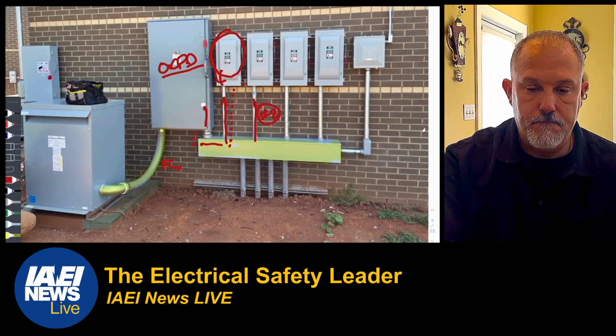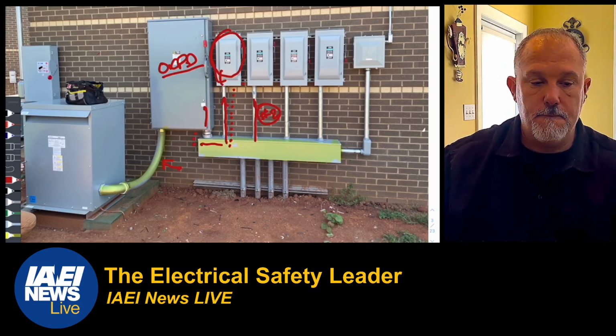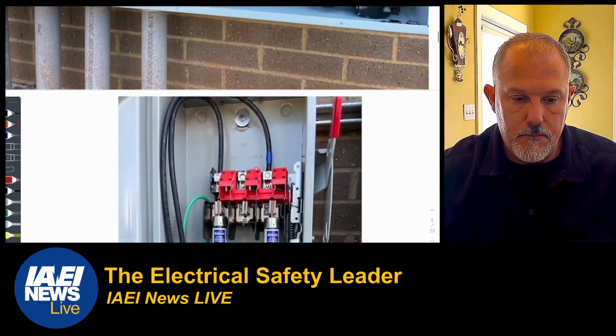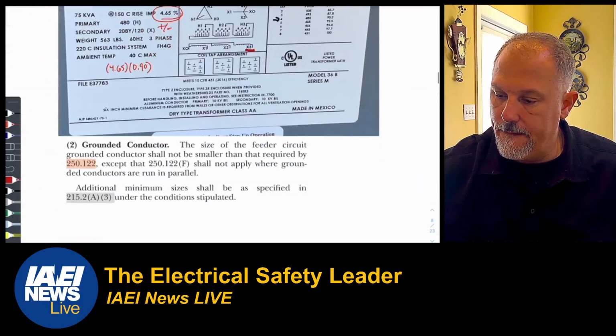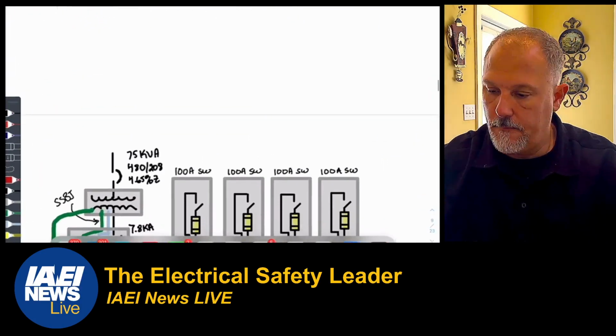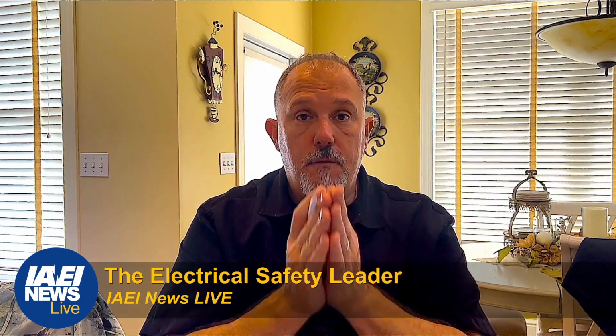All right, so let's just follow this through. Okay, so we've met all the requirements for a feeder tap. All 4 conditions are met. And we've covered the rules around those tapped conductors.